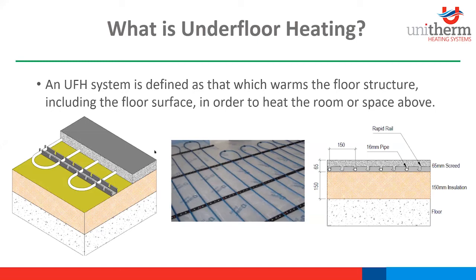So underfloor heating is defined as that which warms the floor structure, including the floor surface, in order to heat the room or the space above. So here you can see a cutout of the standard underfloor heating system. Traditional methods, the floor insulation is bedded on top of your concrete slab, and then there's the vapor barrier placed on top of that.